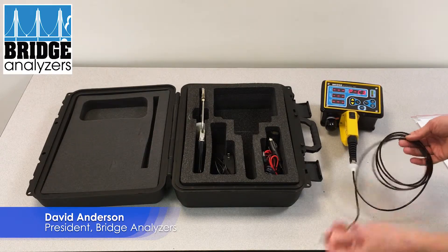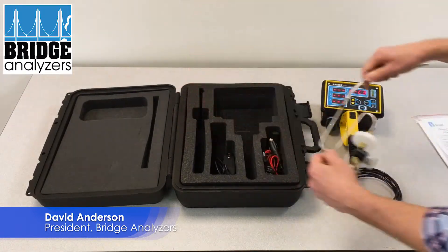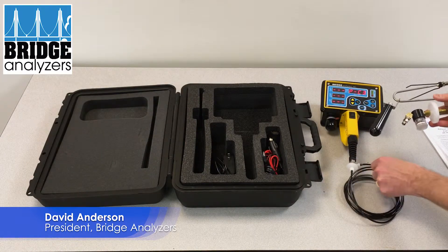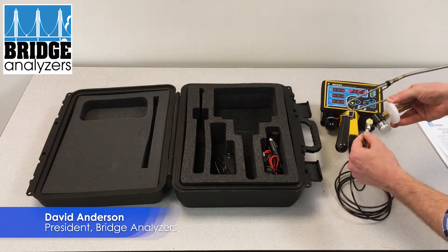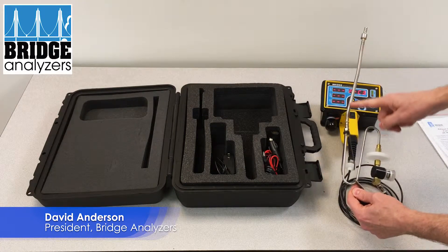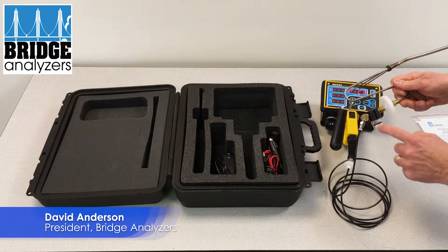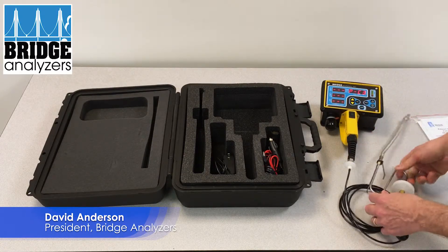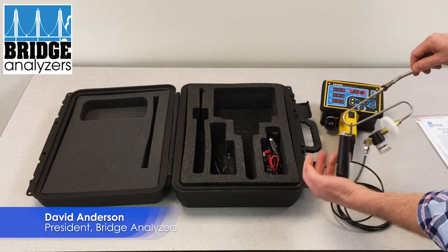The other end gets attached to the compact probe — again it's a luer lock fitting and just goes into the back over here. So now I have a connection from my sample probe through a 50 micron filter into a water trap, through this black line, and then into the analyzer. That's basically our gas path.